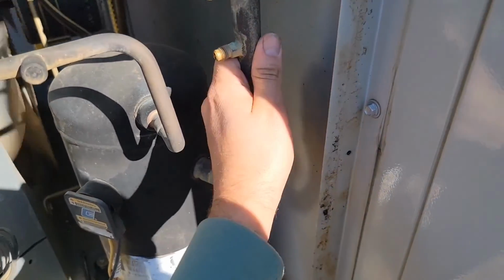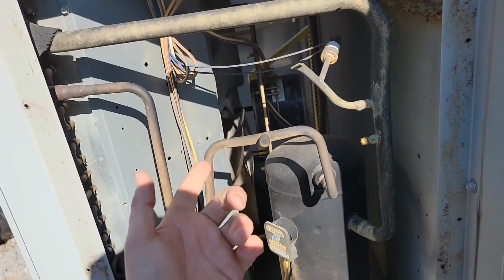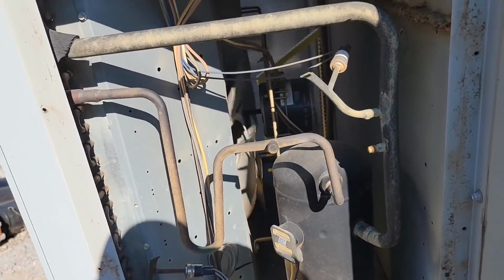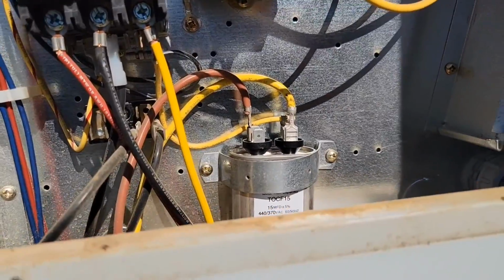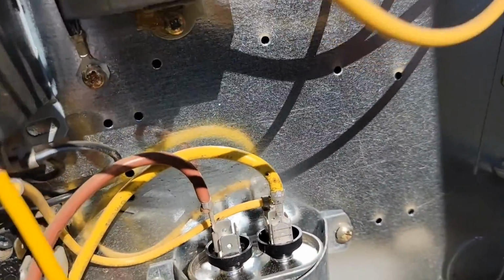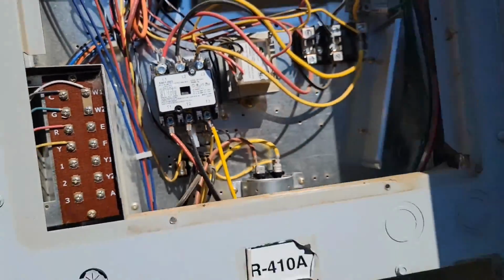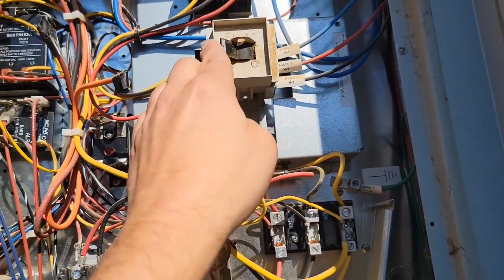So discharge line's hot, suction line's cold, but our outdoor fan is likely the issue. So we got a capacitor right here. Is that bulged? I don't know. We'll check it out. All right, I'm gonna go ahead and turn the breaker off.